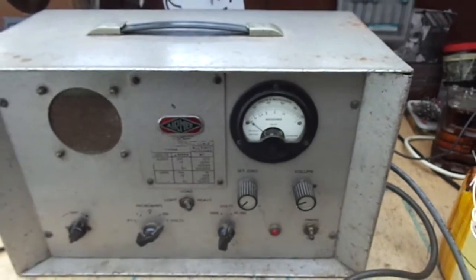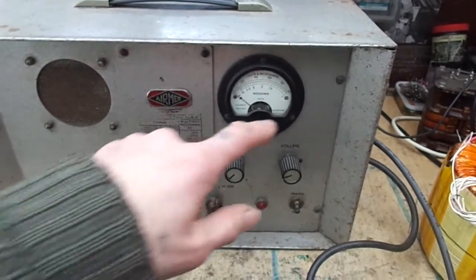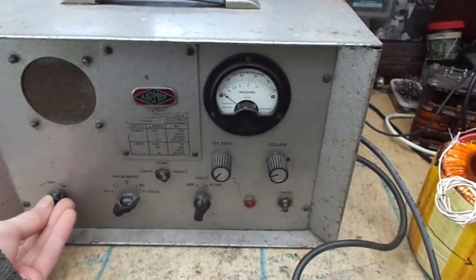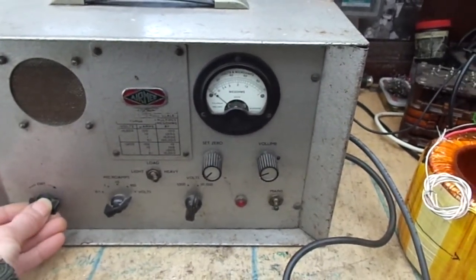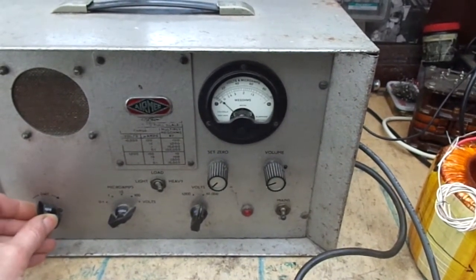Now testing it at 10,000 volts. I'll put you on the thing. Basically what you're listening for is lots of crackles, and if the meter will refuse to go forward. It's cranking it up slowly, takes a while for the EHT to come up.